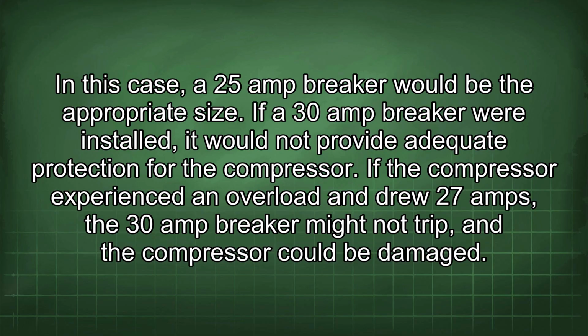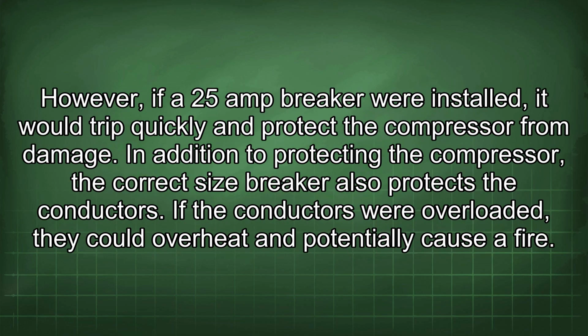If a 30 amp breaker were installed, it would not provide adequate protection for the compressor. If the compressor experienced an overload and drew 27 amps, the 30 amp breaker might not trip, and the compressor could be damaged. However, if a 25 amp breaker were installed, it would trip quickly and protect the compressor from damage. In addition to protecting the compressor, the correct size breaker also protects the conductors.